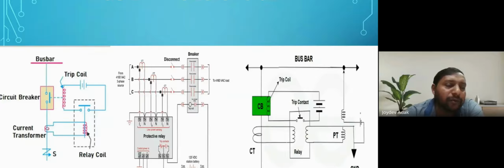After the current transformer and potential transformer, which are the instrument transformers, which replicate the physical system to the relay. Suppose in the physical system the feeder is consuming 200 ampere. The current transformer steps it down to 1 ampere, because our equipment, that is the relay or measuring meter, is designed for low voltage and current, and for actual measuring it multiplies through a multiplying factor. So the current transformer takes the current and replicates the current of the physical system to the relay.